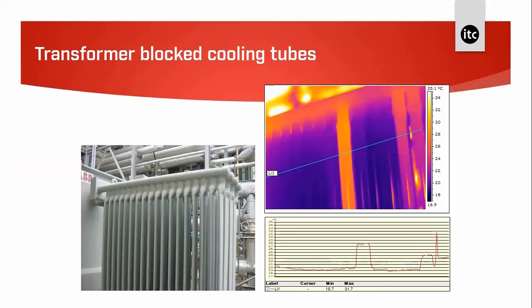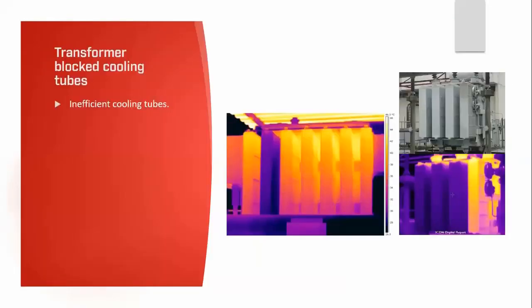Looking at cooling in transformers: most of the cooling tubes in this image are not working. I've put a profile line tool in the software to show the comparison between working and non-working cooling tubes — a great visual, a qualitative approach. In another image, the cooler section on the left reveals a problem with transformer cooling — on further investigation, the valve at the top of that compartment was blocked and unable to do its job.